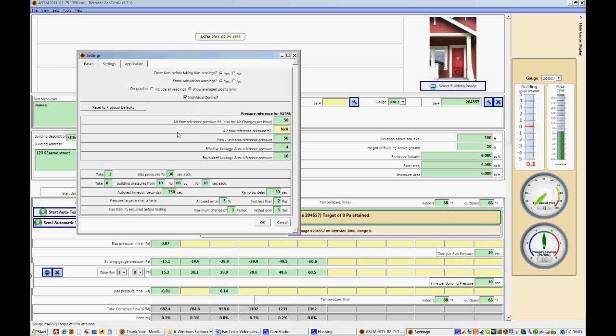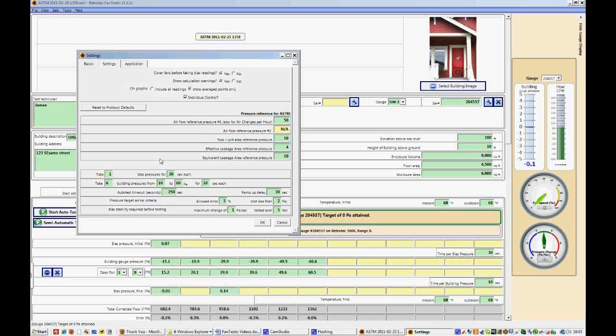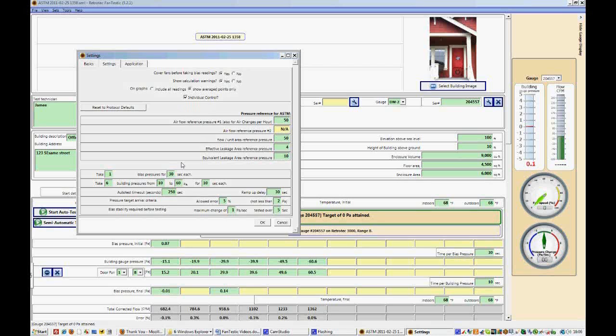However, if you're aware of things that you would like to change, and you know that they still fall within the ASTM protocol standards, you can change them here. So for instance, let's say it was very windy outside, and you're getting bias pressure fluctuations of over one pascal when you were taking your 30 second bias pressure. You'd likely want to stop your test and select a longer bias pressure, maybe for one minute, maybe even longer. That way you're covering a greater range, and you're reducing the amount of bias pressure fluctuation that you can receive in your test. You may also want to take your test pressures for a longer period of time, so perhaps a minute each. That way you're getting more accurate data.